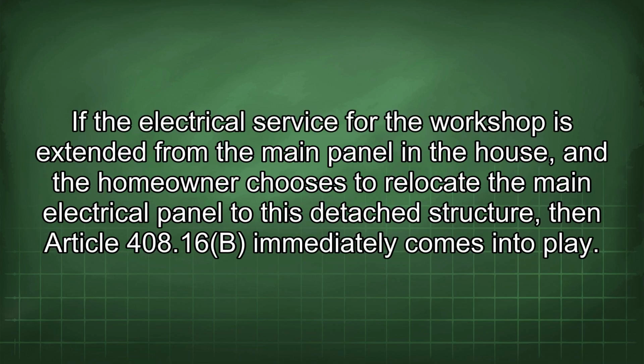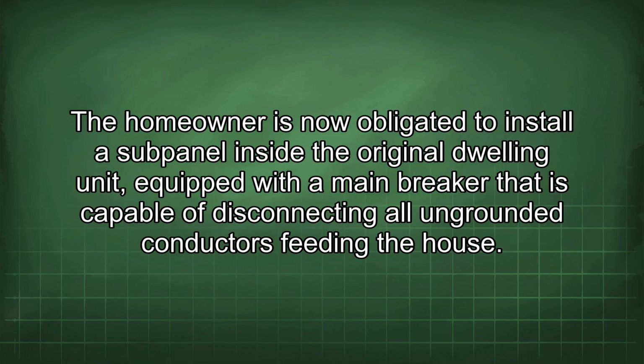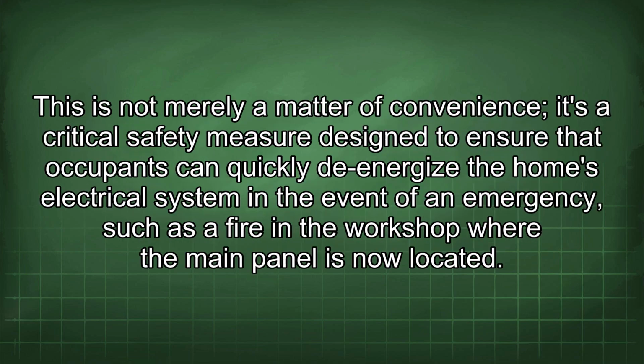If the electrical service for the workshop is extended from the main panel in the house and the homeowner chooses to relocate the main electrical panel to this detached structure, then Article 408.16b immediately comes into play. The homeowner is now obligated to install a subpanel inside the original dwelling unit, equipped with a main breaker that is capable of disconnecting all ungrounded conductors feeding the house. This is not merely a matter of convenience, it's a critical safety measure designed to ensure that occupants can quickly de-energize the home's electrical system in the event of an emergency, such as a fire in the workshop where the main panel is now located.